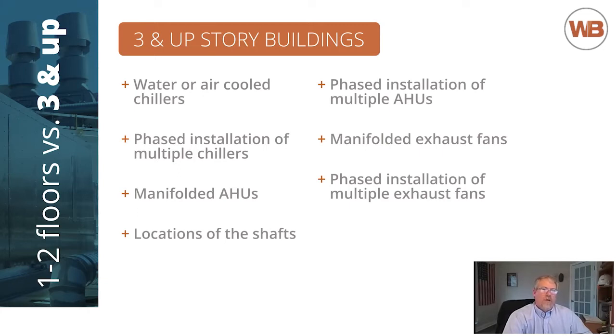So that you can have modular chillers, modular air handling units, and modular exhaust fans. The reason you want to think about those components is that they're the biggest components that are going to occupy space. But if you do it in a systematic way, you can add an air handling unit and a chiller, or an air handling unit and an exhaust fan, per floor, and buy them as you lease your buildings up. Then they would have a shared system with reliability and/or redundancy.